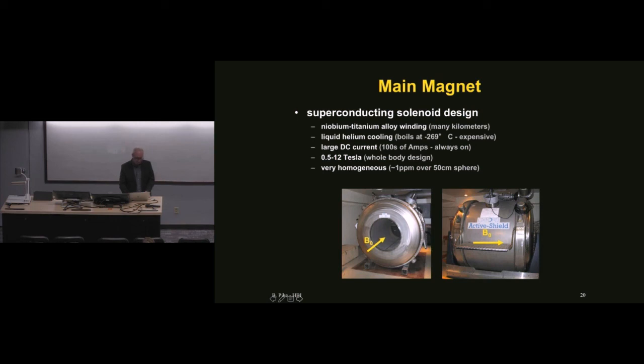So the bare magnets, these systems, the rule of thumb is about $1 million a Tesla. So if you want a 3 Tesla magnet, they're around 3 million. A 1.5 Tesla is around 1.5 million. They tend to go up a bit non-linearly after that, probably 10 million for a 7 Tesla.